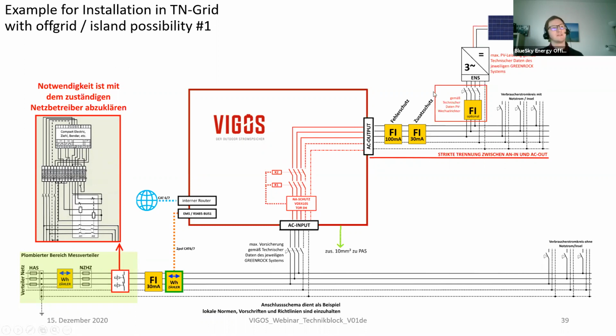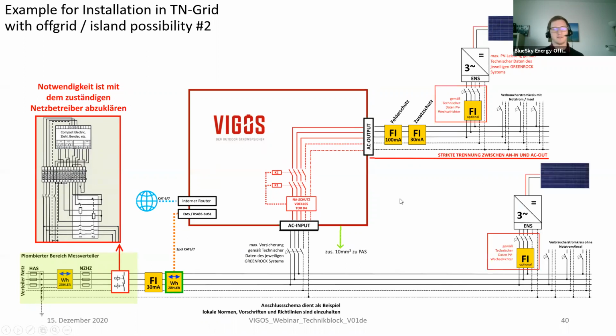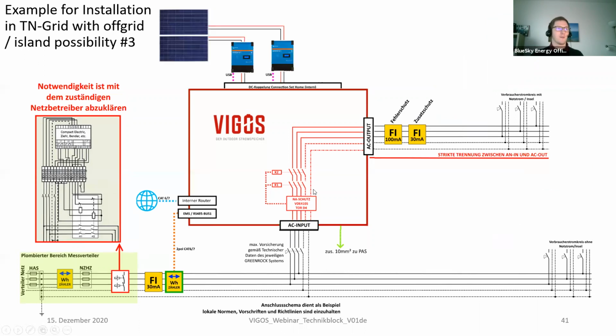So if the PV system is too big, it could also be that you have an installation like this. This is a PV inverter which fulfills the maximum power available from the Vigos. And in here you can choose whatever size of PV inverter you want. Here the function stays the same. But if you have this grid failure at midnight and the battery is already empty at 4, this will not give you an off-grid functionality. So for that, you need a DC coupling, which can be displayed like that.